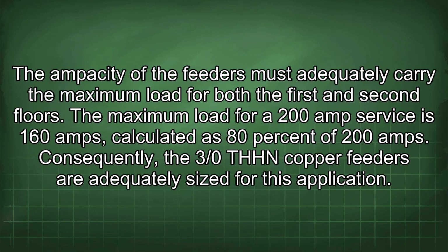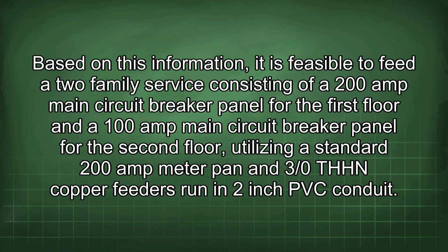The ampacity of the feeders must adequately carry the maximum load for both the first and second floors. The maximum load for a 200 amp service is 160 amps, calculated as 80% of 200 amps. Consequently, the 3/0 THHN copper feeders are adequately sized for this application. Based on this information, it is feasible to feed a two-family service consisting of a 200 amp main circuit breaker panel for the first floor and a 100 amp main circuit breaker panel for the second floor, utilizing a standard 200 amp meter pan and 3/0 THHN copper feeders run in 2-inch PVC conduit.